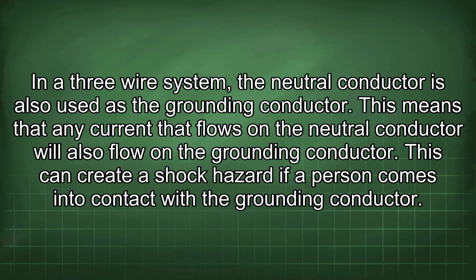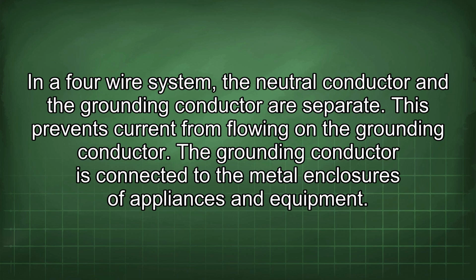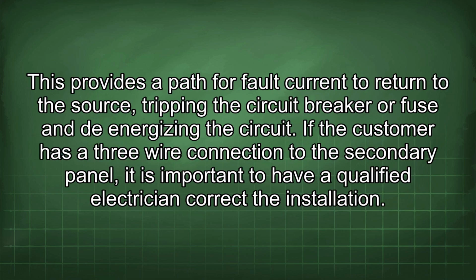This can create a shock hazard if a person comes into contact with the grounding conductor. In a 4-wire system, the neutral conductor and the grounding conductor are separate. This prevents current from flowing on the grounding conductor. The grounding conductor is connected to the metal enclosures of appliances and equipment.